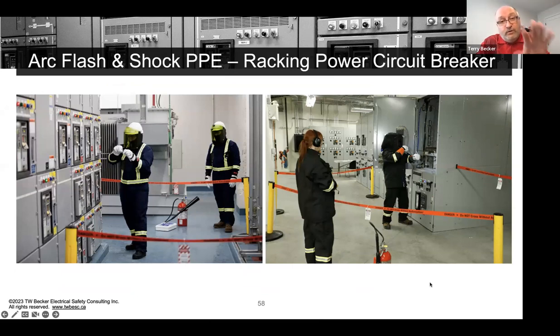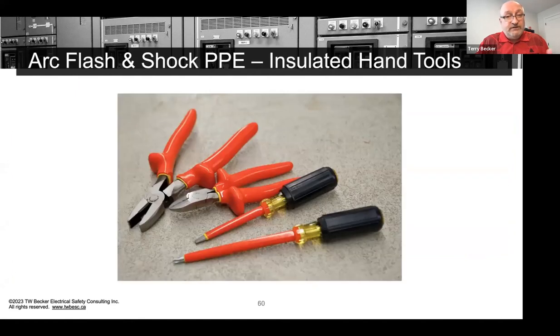For these work tasks, we want the electrical safety watch. Workers do not need a safety watch for standard work tasks. They can work alone following your company's policies and procedures, for voltage testing, current measurements, standard diagnostics. The rubber insulating gloves, as I pointed out, we need to get those on a worker if their shock risk assessment indicates that they have identified what's called the restricted approach boundary. Once you have that restricted approach boundary, which is 12 inches for low voltage electrical equipment, and your hands go in the box, then these would be worn by policy. Insulated hand tools required.